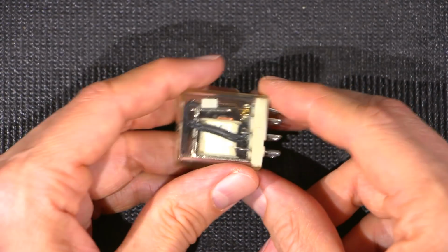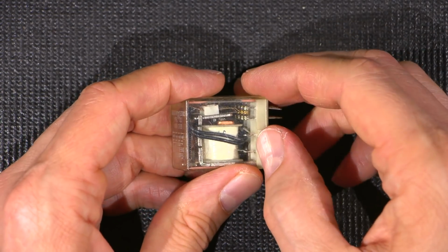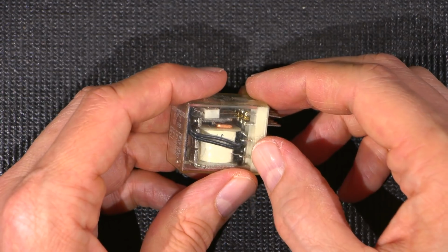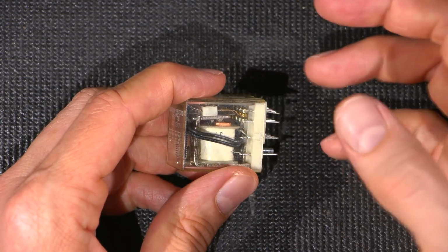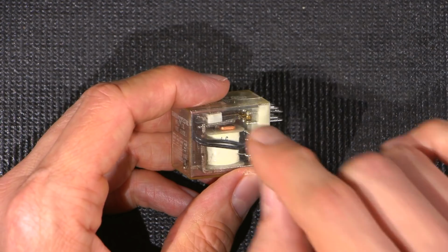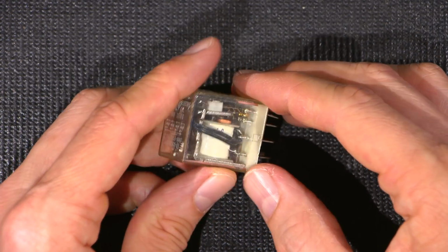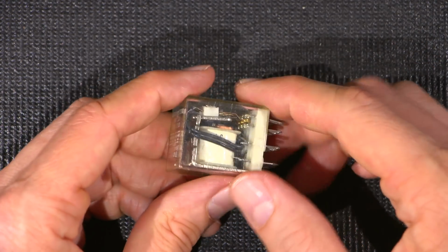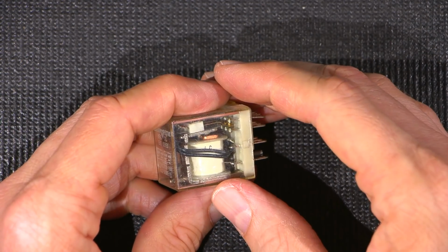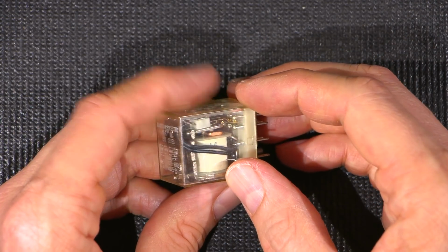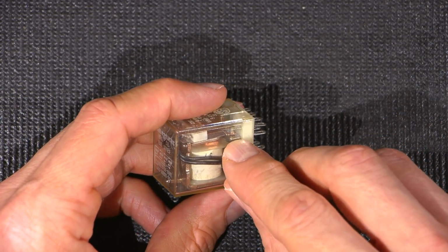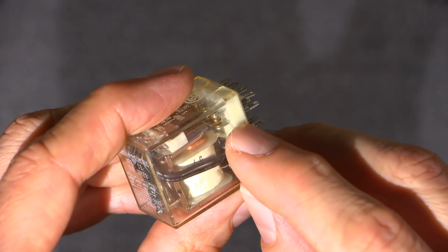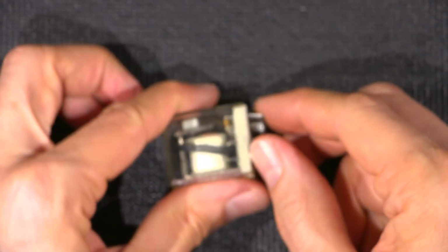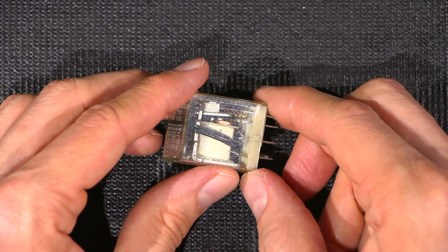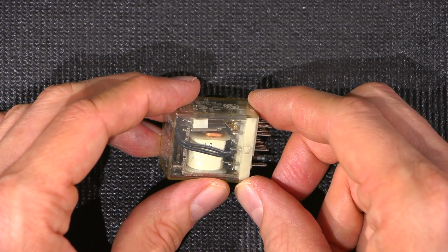Okay, but in a case like this, what you want to do, if the contacts are bad, you can usually take these things apart, and what I do is I try and polish them. All right, so if they're really badly pitted, sometimes you need to sand them, or you can use a burnishing tool, an actual relay burnishing type of tool, and you can clean them up like that. If you don't have to sand them, I would suggest not, because a lot of the times they're plated. The actual contact itself inside has a plating on it. And if you take the plating off, you'll find that the contacts will stick, or they'll get intermittent again in a short period.